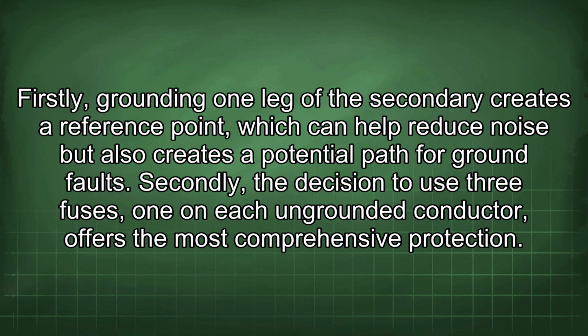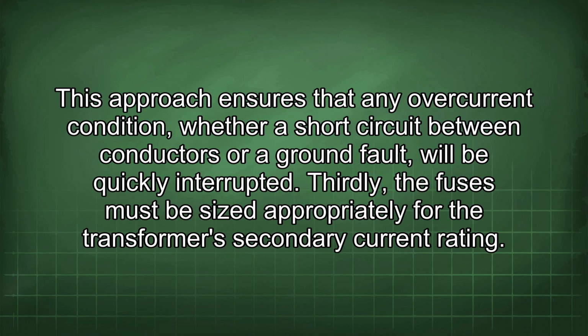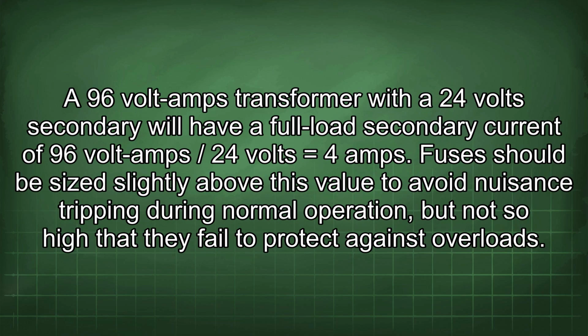Secondly, the decision to use 3 fuses, one on each ungrounded conductor, offers the most comprehensive protection. This approach ensures that any overcurrent condition, whether a short circuit between conductors or a ground fault, will be quickly interrupted. Thirdly, the fuses must be sized appropriately for the transformer's secondary current rating. A 96 volt-amp transformer with a 24 volt secondary will have a full load secondary current of 96 volt-amps / 24 volts equals 4 amps.